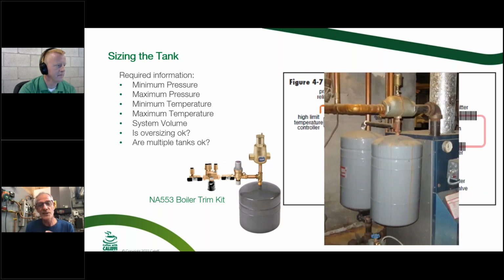So what you'll find is if you want to use one of the online calculators, if you click on the commercial one, it lets you put in more of this information than just the residential. It just says what size is your boiler, kind of in the temperature range, and gives you a choice. So this is an option of using 2 expansion tanks instead of 1. They'd both have to be pre-charged properly.